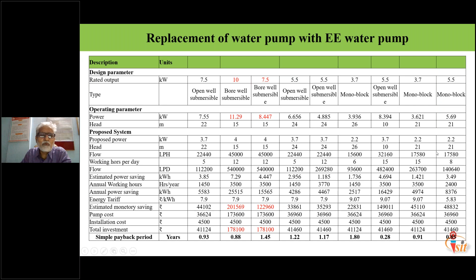This is how we do the analysis: we take measurements, study the pump, and recommend an energy efficient substitute for that particular application. We suggest the calculated payback period and recommend replacement, so that once the cost is recovered after 1 or 1.5 years, it becomes a recurring benefit. They get this much saving every year from these two pumps.